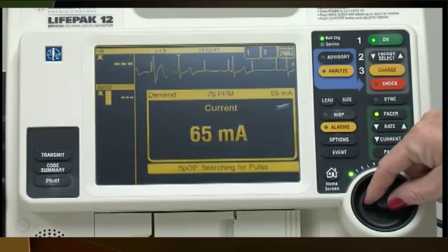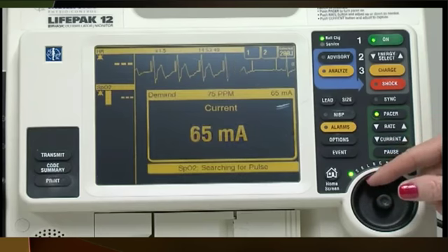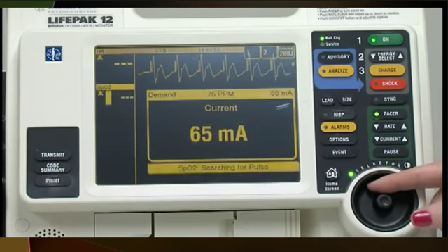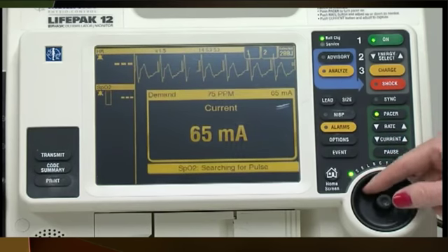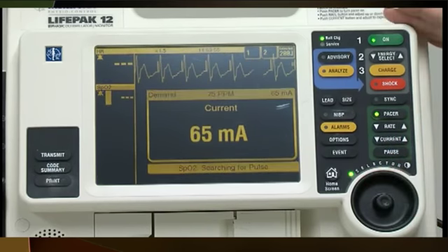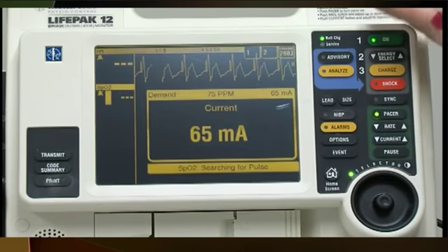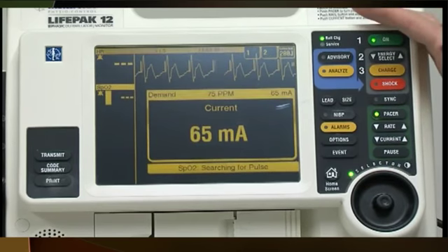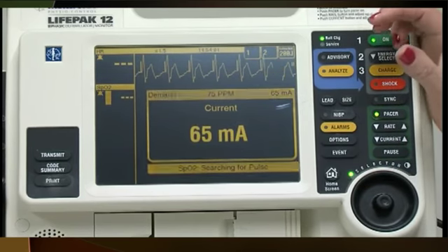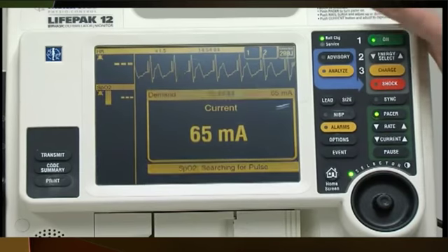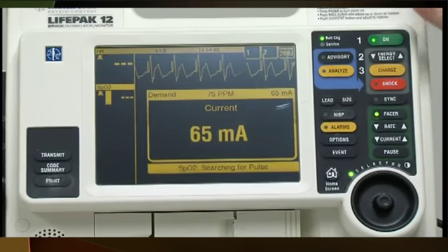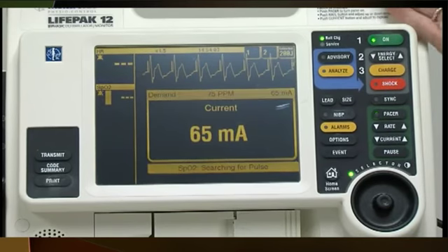Remember, this is an external device, so your milliamps are going to be a lot higher than what they are if you have a transvenous. I now have one-to-one capture. This would be the number that I would look for my stimulation threshold. This number is 65, but let's say that in an external or for a transvenous, it really is 6.5.